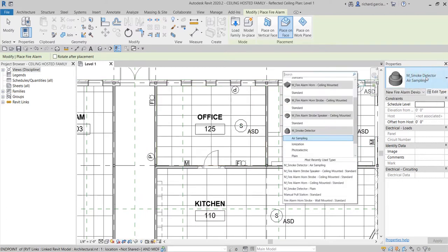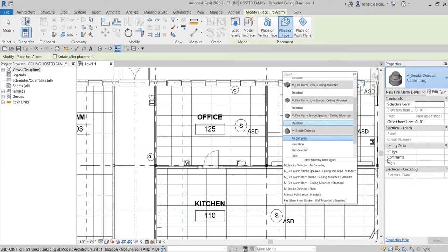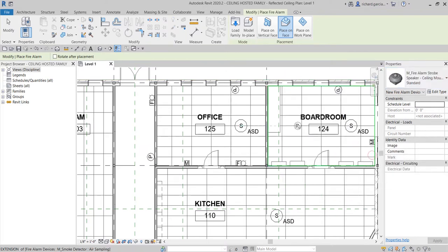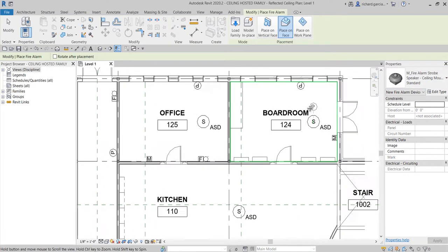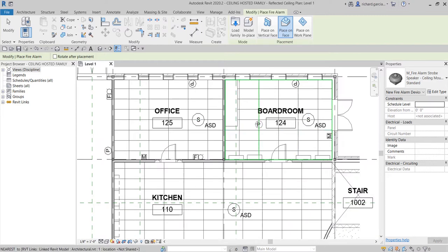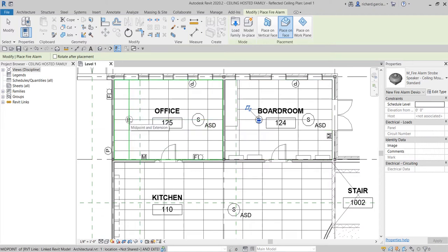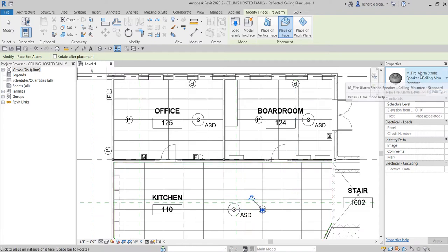Now I'll select the Fire Alarm Horn Strobe Speaker from the drop-down. Make sure 'Place on Face' is selected since we're placing on the ceiling. One important note: if you or the architect removes the ceiling, any family hosted on that ceiling will be deleted as well. I'll place one here — there's my fire alarm strobe speaker.